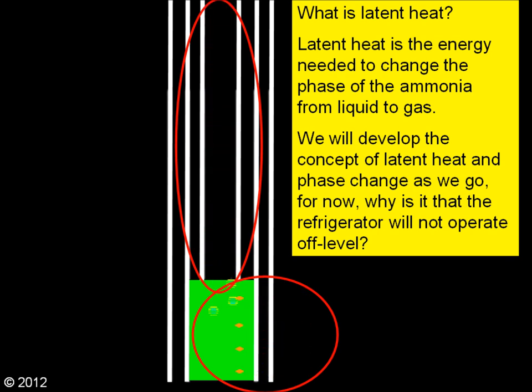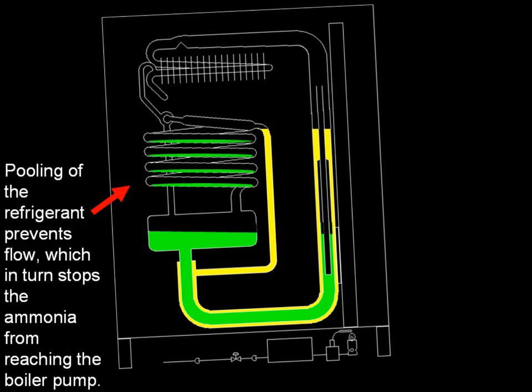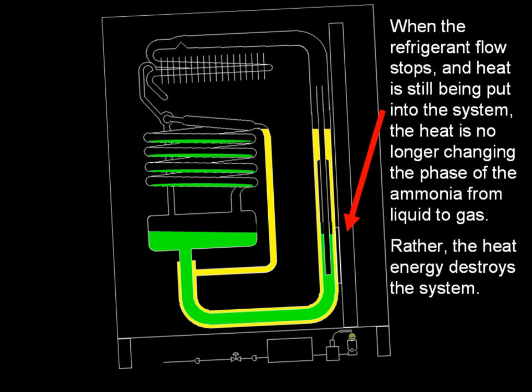Why is it that the refrigerator will not operate off-level? The refrigerator cannot be operated off-level because the refrigerant pools in the process tubing. Pooling of the refrigerant prevents flow, which in turn stops the ammonia from reaching the boiler pump. When the refrigerant flow stops and heat is still being put into the system, the heat is no longer changing the phase of the ammonia from liquid to gas — rather, the heat energy destroys the system.